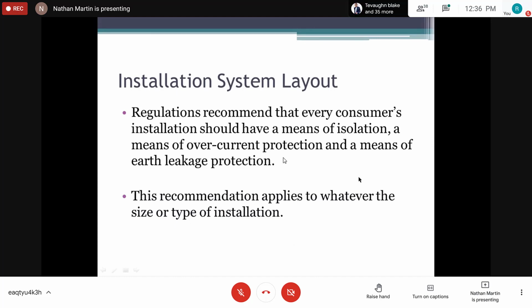Now, regulation recommends that every consumer installation should have a means of isolation, whether it be the IEE regulation, the NEC regulation, or our local regulation. It states that each consumer, and we're talking about industrial, commercial, and residential, right? So don't think of a consumer as just your home or a small installation. Whether it's small, medium, or large, the regulations state that it must have a means of isolation, meaning it must have a main circuit breaker, right?